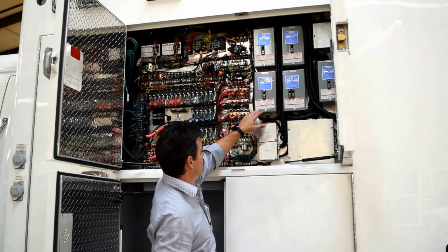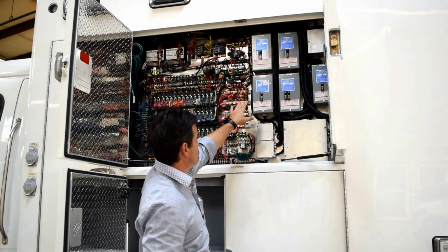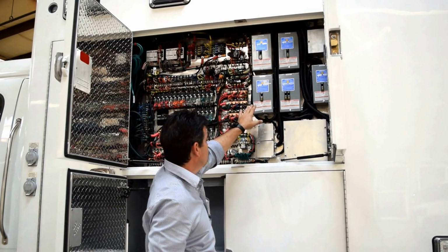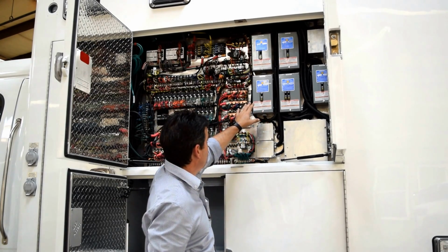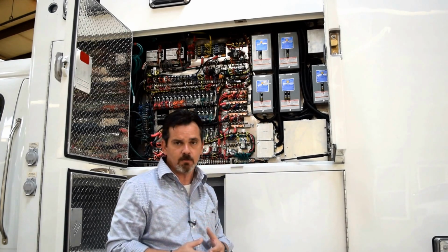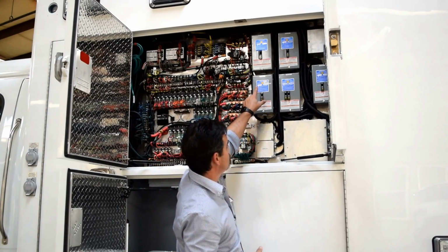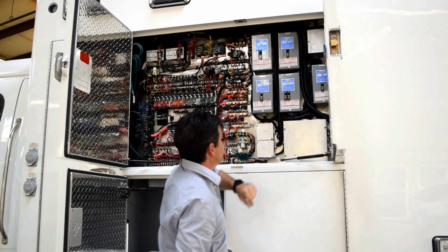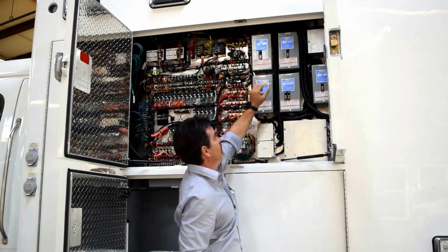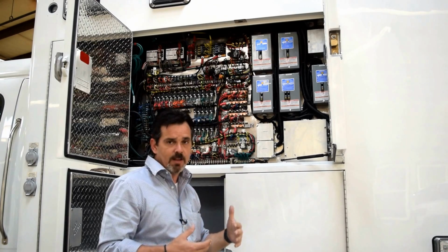For instance, this particular breaker box here controls the ceiling outlets, the EMT action area outlet, the workstation outlet strip, and the aft action area strip, which is on the street side interior of the vehicle. So that's addressing all the interior outlets of the vehicle. And it's connected to shoreline B as it's labeled here. And same thing, if you look above, it's labeled shoreline B, this breaker here, and the only breaker in here is for one of the rooftop air conditioners. That breaker is for the rooftop air conditioner.